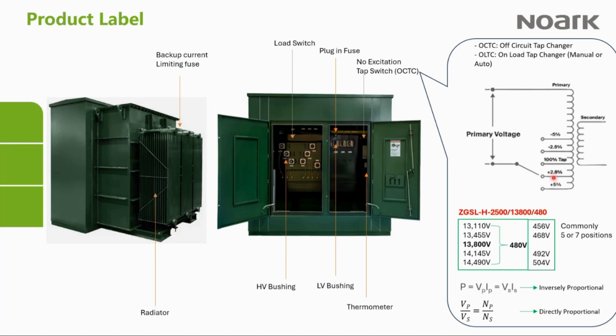So why do we need that in a transformer? Let me try a simple example here. Whenever you're trying to bring power into a transformer, the power comes in at a primary voltage. In this case, we're talking about a step-down transformer. And then on the secondary side, what you expect is that the voltage is going to be reduced to the level that you need. For example, if you have a 2,500 kVA transformer, and the primary is 13,800 volts or 13.8 kilovolts, we expect to have 480 volts on the secondary side.